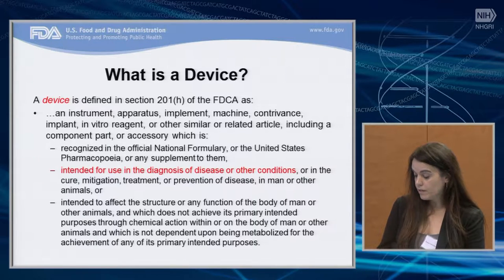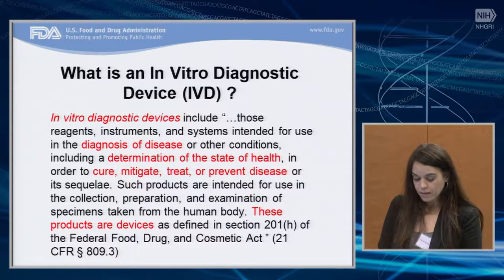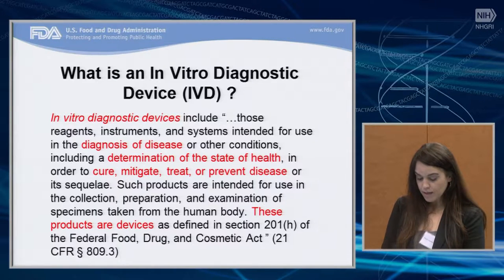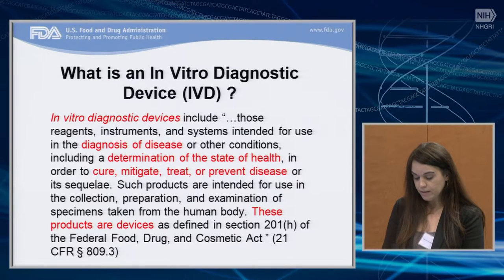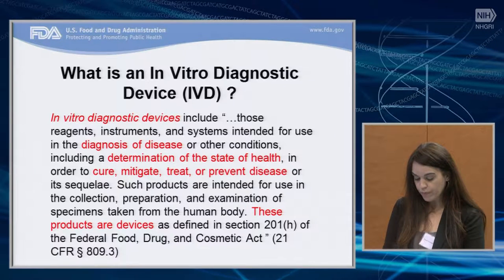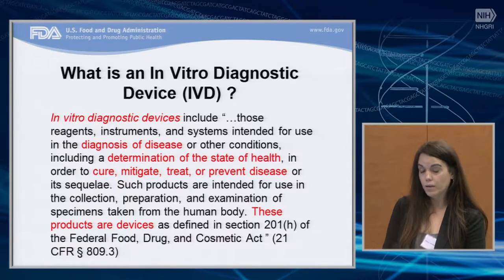So, this is the definition of the device from the Food and Drug Act. The in vitro diagnostic device includes those reagents, instruments, and systems intended for use in the diagnosis of disease or other conditions, including a determination of the state of health in order to cure, mitigate, treat, or prevent disease or its sequelae. Such products are intended for use in the collection, preparation, and examination of specimens taken from the body. These products are devices as defined in the Federal Food, Drug, and Cosmetic Act, and this definition comes from 21 CFR 809.3, our code of federal regulations.